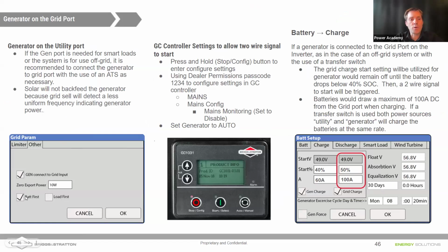This priority setting should always be battery first, and the zero export power is a setting for the tolerance of power that can flow back and forth between the grid. The GC controller settings, again, as before, we're enabling two-wire signal to start and disabling auto main sensing.